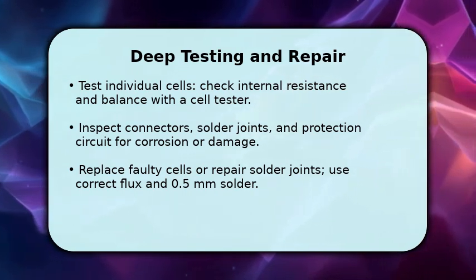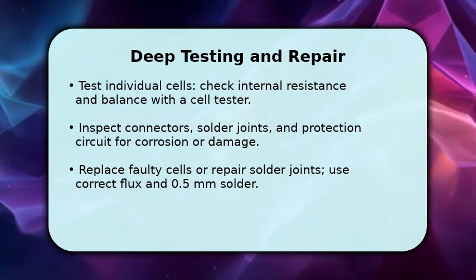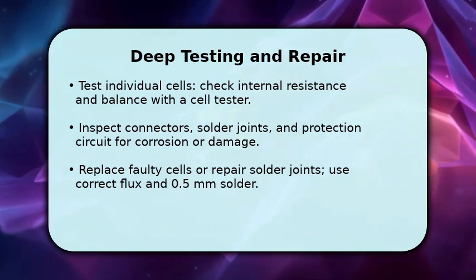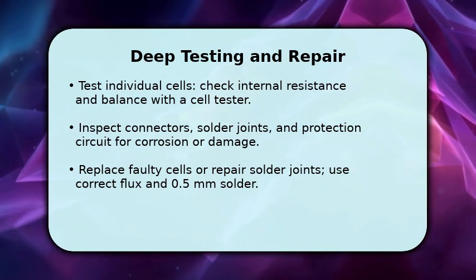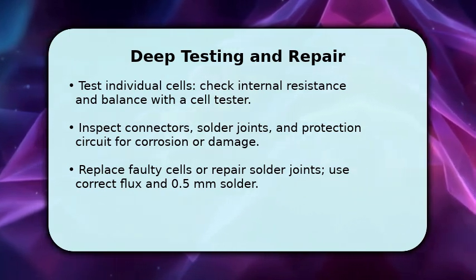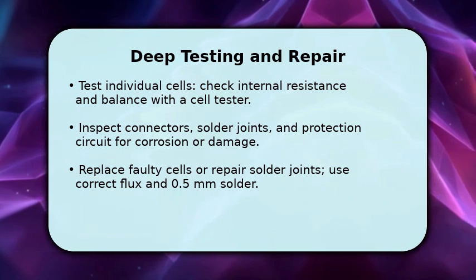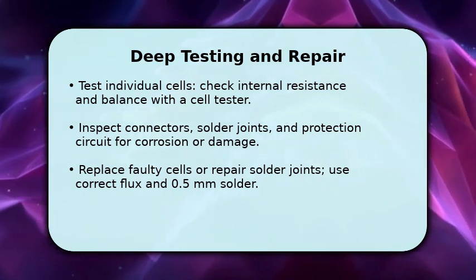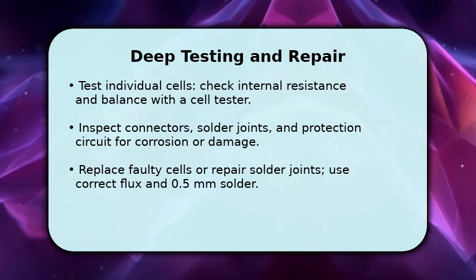If connectors or solder joints show corrosion, clean and reflow them, because poor connections produce heat and voltage drop. Once you replace faulty cells or repair joints, charge slowly to balance cells and verify stable voltages before reassembly.